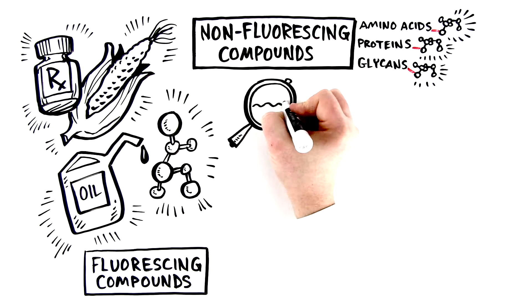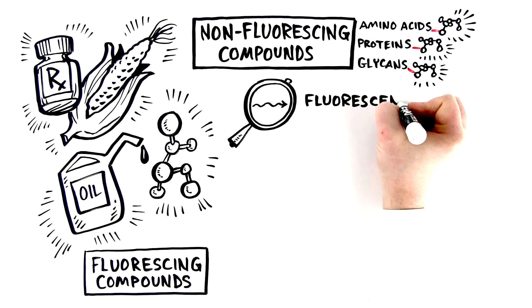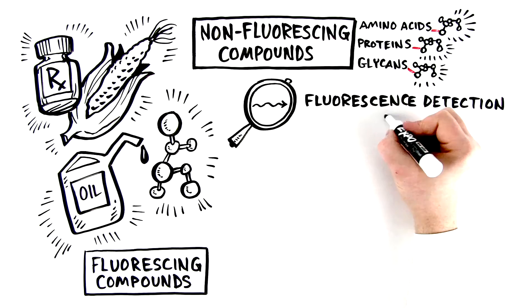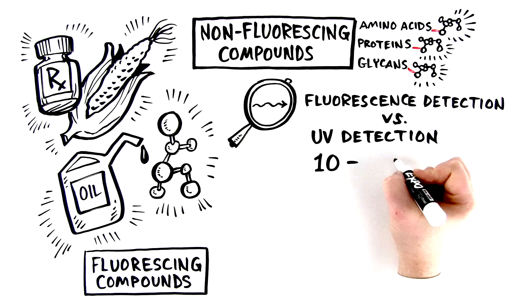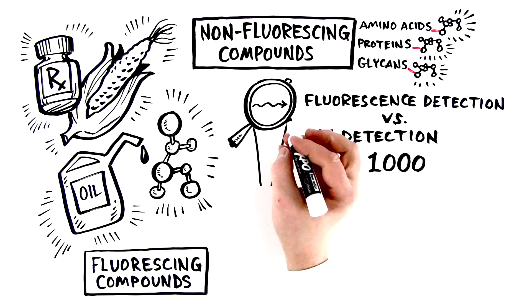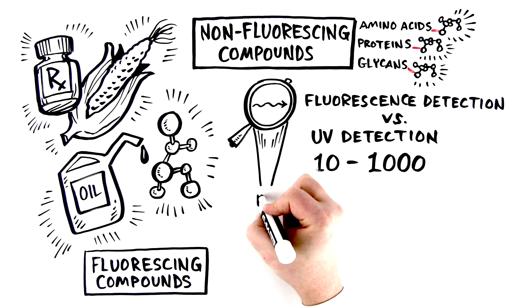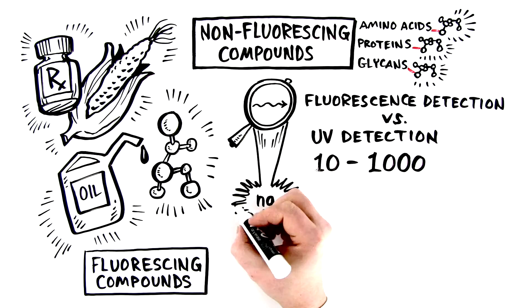This way, these compounds become visible for a fluorescence detector. By detecting the emitted light, fluorescence detection is much more sensitive than UV detection by a factor of 10 to 1000. This allows detection of trace amounts of compounds down to the nanogram level.